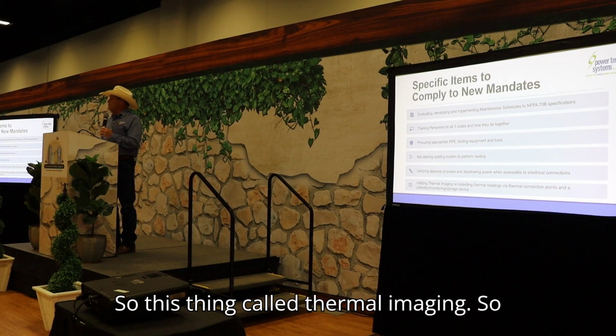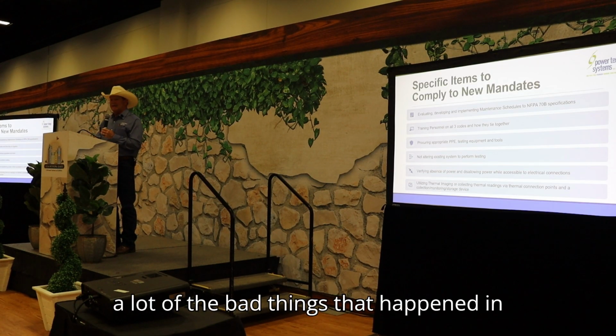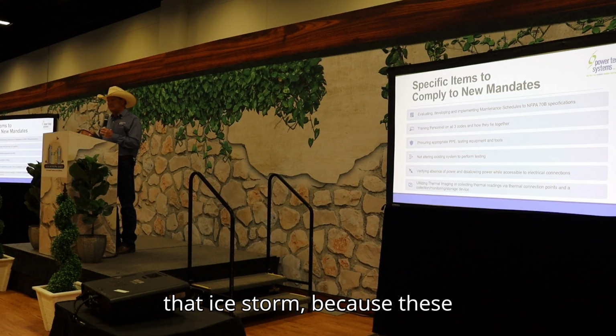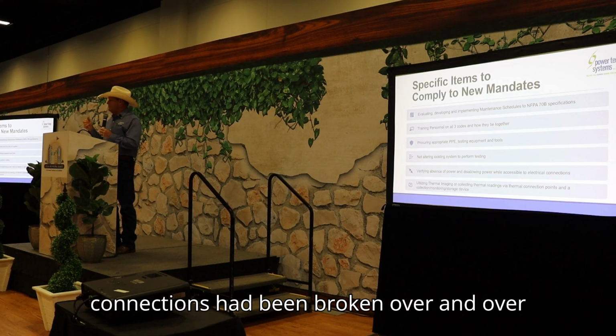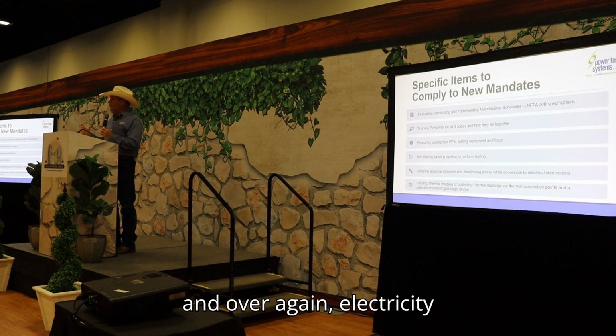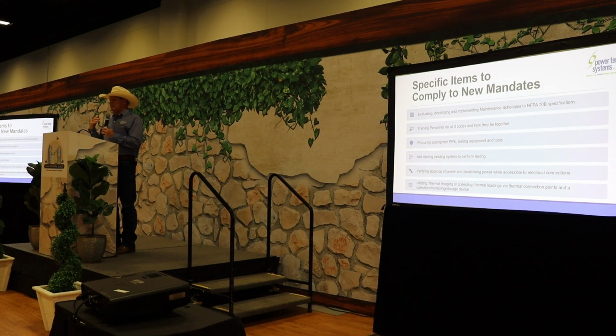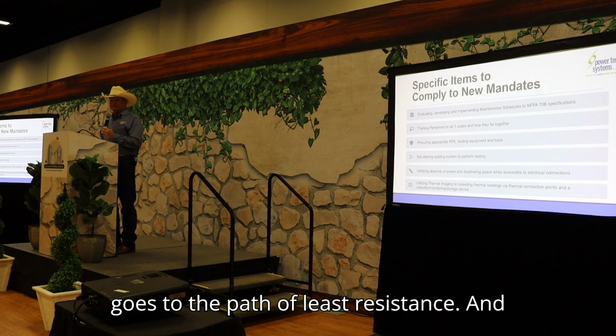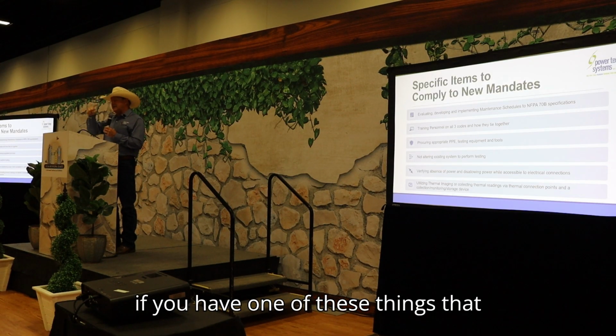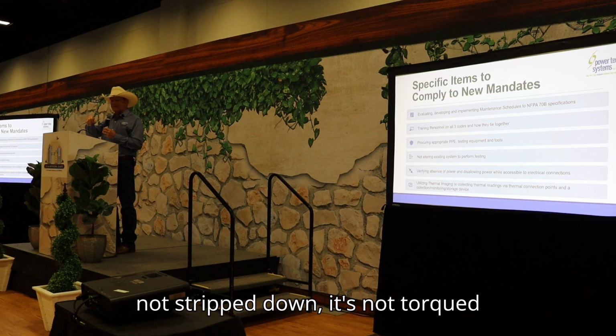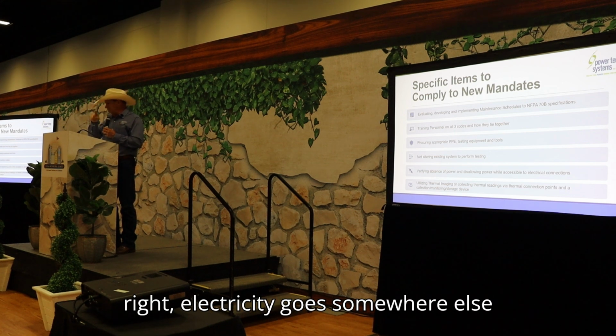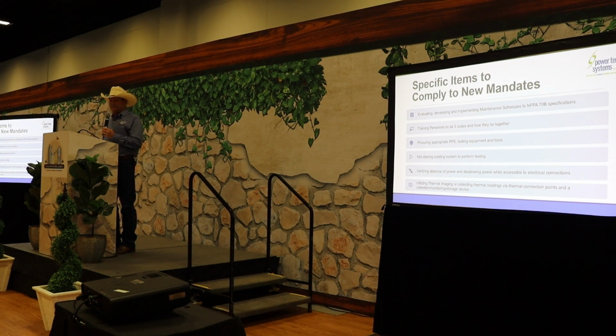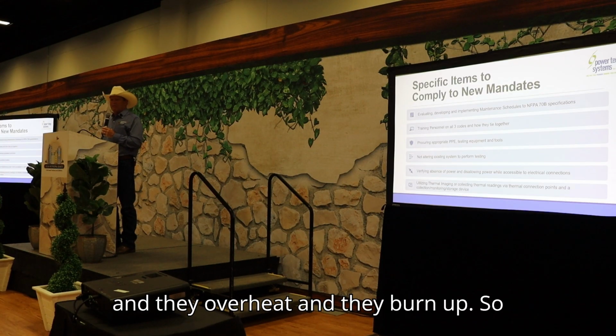So there's a thing called thermal imaging. A lot of the bad things that happened in that ice storm happened because these connections had been broken over and over again. Electricity goes to the path of least resistance. And if you have one of these connections that's been done over and over, it's not stripped down right, it's not torqued right, electricity goes somewhere else. And they overheat and they burn up.